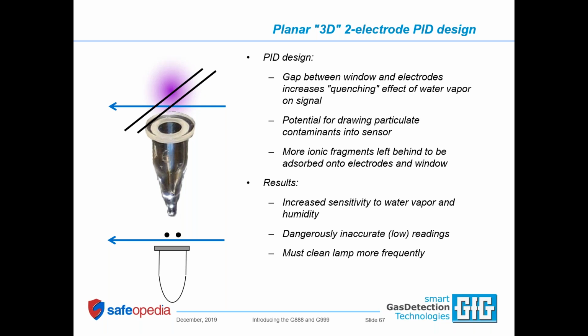Well, the problem is that gap is full of atmosphere, and that atmosphere always includes some water vapor molecules. Under temperature conditions where the humidity is high, the photons of ultraviolet light hit those molecules of water. The water molecules absorb the photons, but the molecules are not ionized. What that means is they quench the signal. And this is serious. On a humid day, the readings from this kind of sensor can be 30, 40 or more % lower than the true concentration.